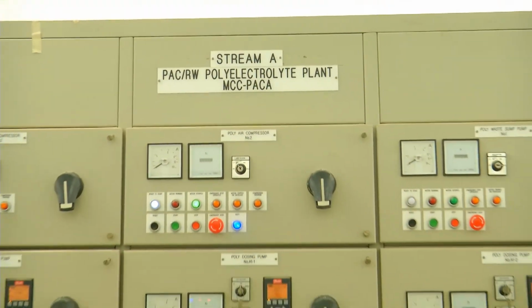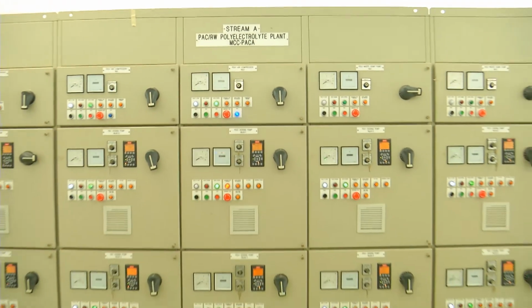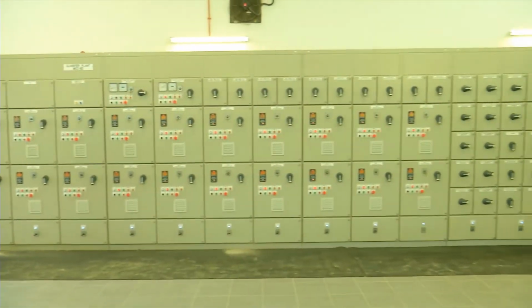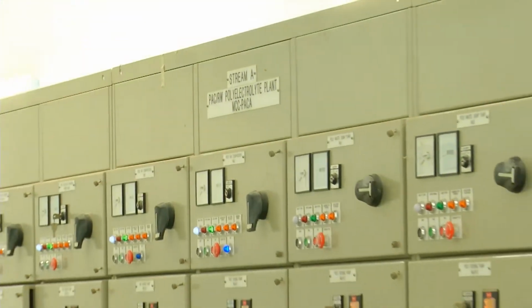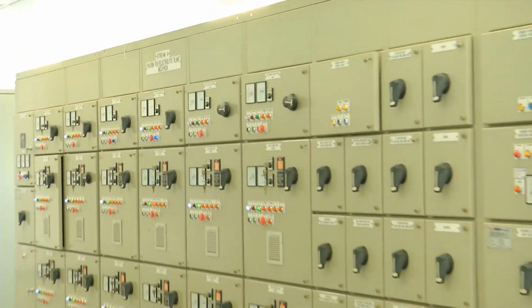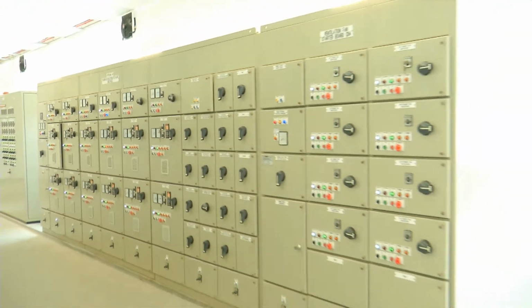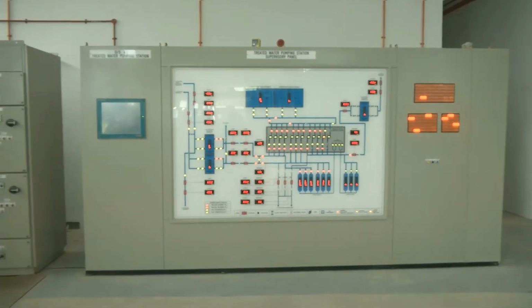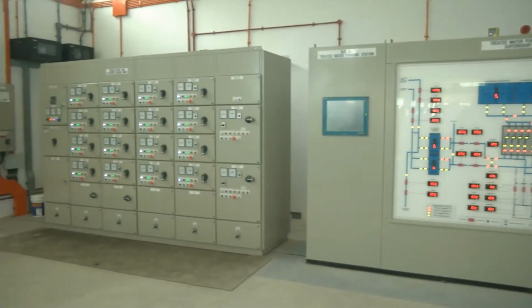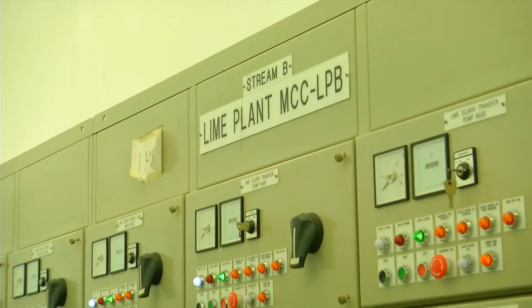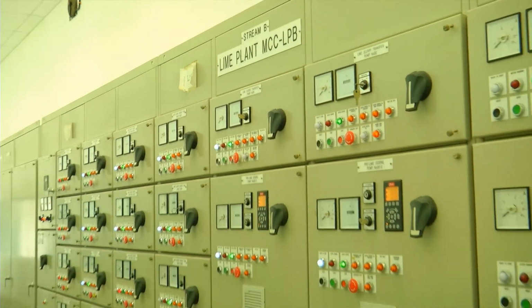Motor Control Center, MCC, is an assembly to control all electric motors in a central location. It consists of multiple enclosed sections, having a common power bus and with each section containing a combination starter, which in turn consists of motor starter, fuses or circuit breaker, and power disconnector.